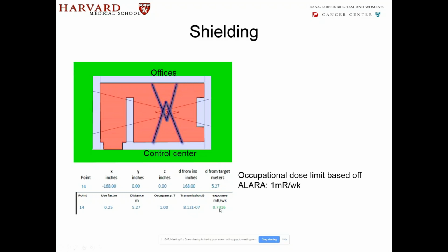The other thing is, if you look at the diagram, this shows a completely open field, but most or all of our treatments use MLCs, so the field is never actually open this much - only tiny small regions are open at any given time. The calculation doesn't include MLC leaves, so this is probably more like 0.2 milliroentgen per week or less that one gets from this kind of shielding.